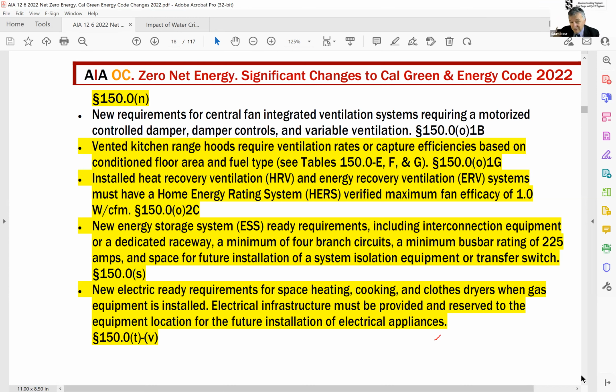Now remember, the energy storage system must be there, with all the interconnections, dedicated raceways, and elements. You actually have to put a little box and say please don't put anything there. You need 4 branch circuits just for that. The bus bar rating for the panel must be 225. You must put in a transfer switch, because otherwise it goes pop, pop, pop, pop. The transfer switches I was studying a couple months ago come in a complete package with the system.